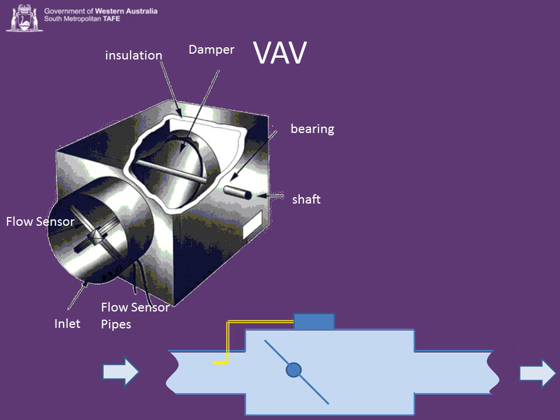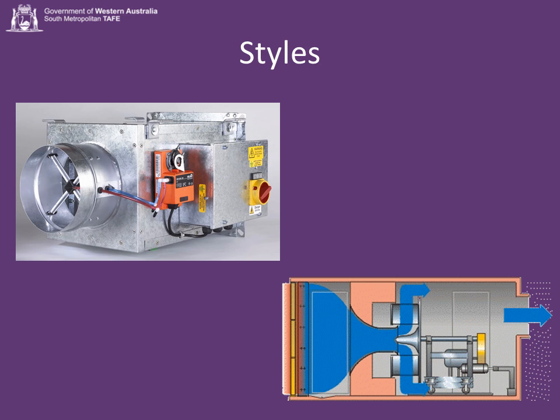You stick an actuator on the shaft, you stick a controller on the whole thing, you stick a temperature sensor in the room, call that the space temperature sensor, and we're good to go. We're now able to control rooms to an individual temperature. There's two main types of VAV. The first type, on the top left, the big silver thing, is the style I've been describing, where you have a damper which opens and closes the duct to let more or less air through.